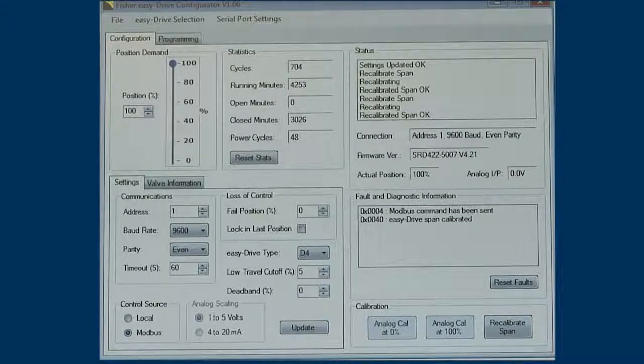Next, we are ready to calibrate using the analog control signal. On the configuration software, check local within the control source box. Make sure that if you intend using a 4 to 20 milliamp signal, that the 4 to 20 milliamp analog scaling is set. Then click Update.